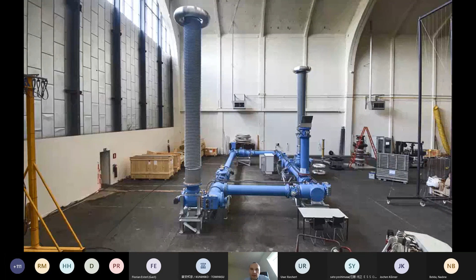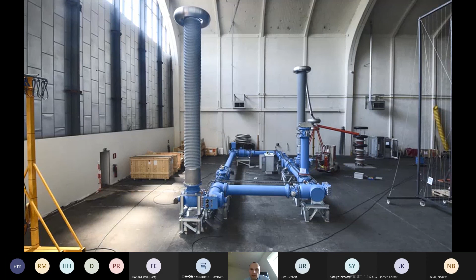And what you can see here is now a time-lapse video of the installation and commissioning on site in Arnhem. You can see we start with the steel supports, and then all the factory modules arrive and are connected together to form the ring. Here, of course, the cleanliness is observed by the installation team. And you see how the ring is building up. After that, the crane comes in and connects the bushing and the RC divider. And after that, we connect all the secondary technology. And then it's time for the commissioning test, which is done with an AC resonance system. And after that was successful, the test pole was ready to start the main test.